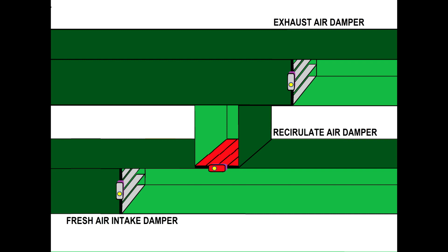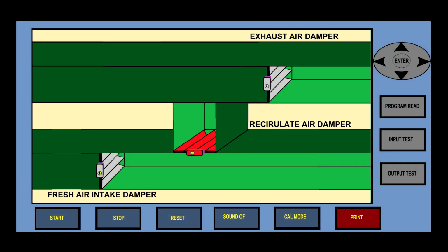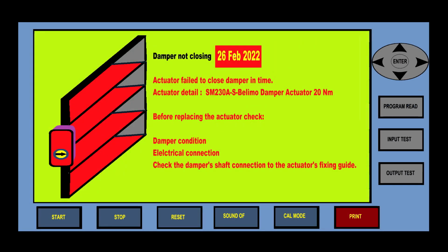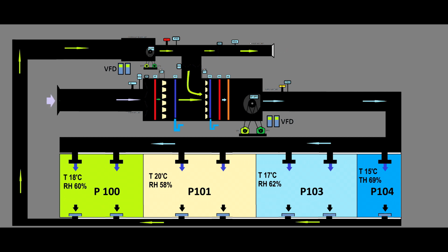If you have a problem with the recirculated air damper, you lose the possibility to recirculate the air, and this is not good. Now the HMI will show you the fault. If the programmer writes great software and the control philosophy engineer knows his job, he will put the right program into the PLC. Again, the HMI will show you which damper is faulty. It will give you some details about the damper and some instructions on what to do. But again, this is a choice. It is up to how the control philosophy engineer will choose to do his job.